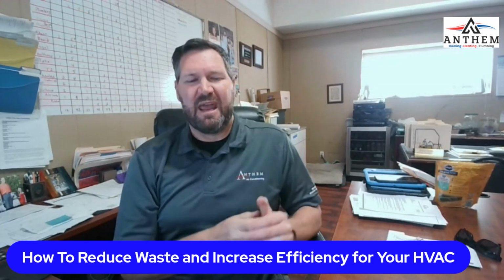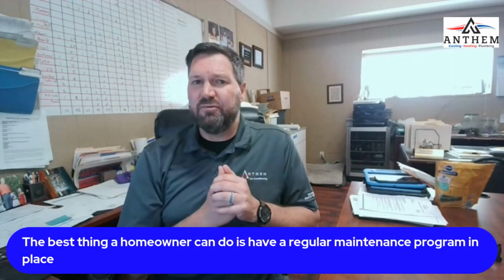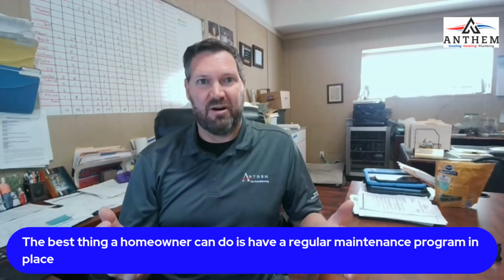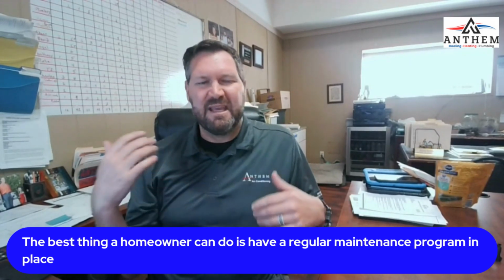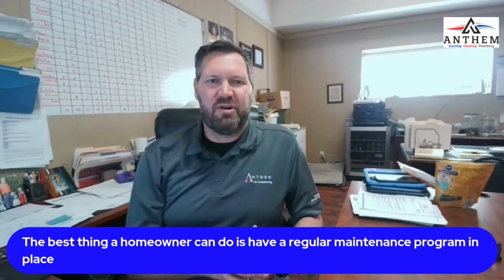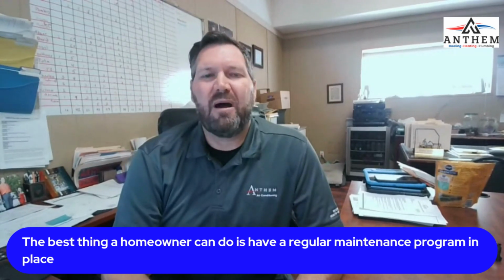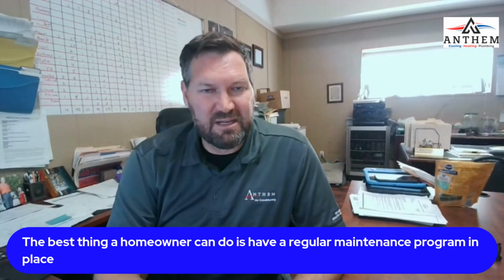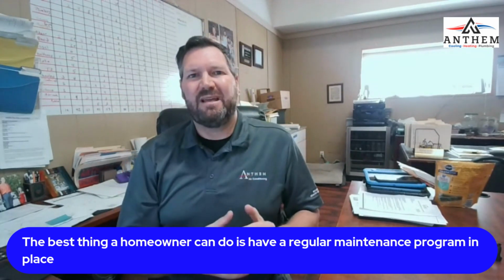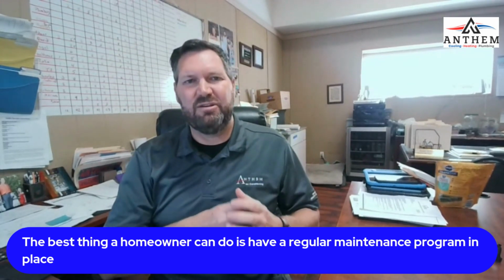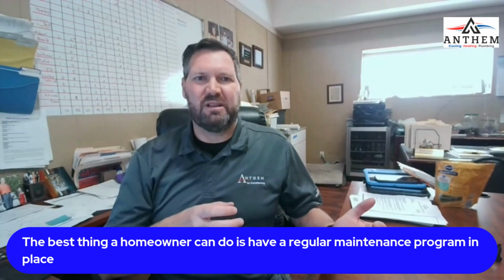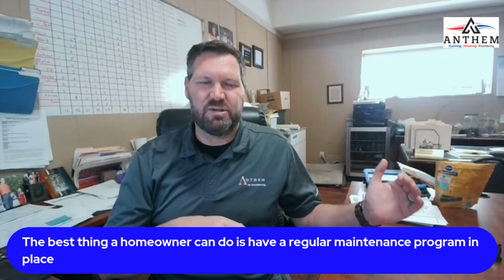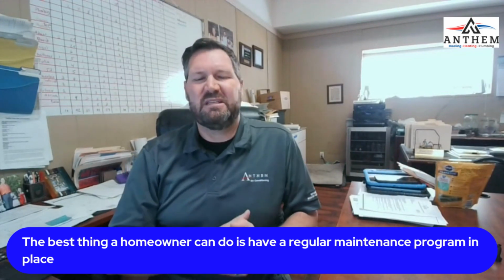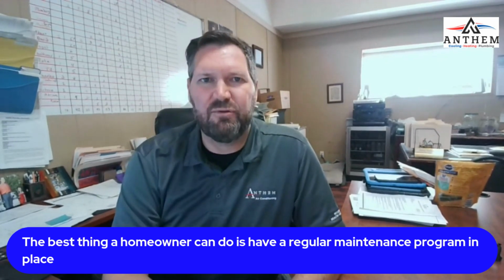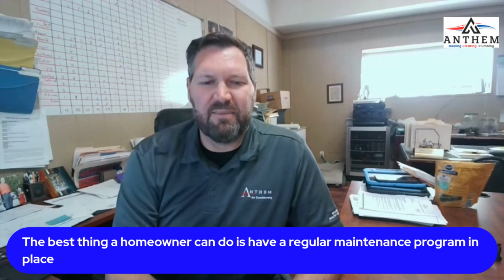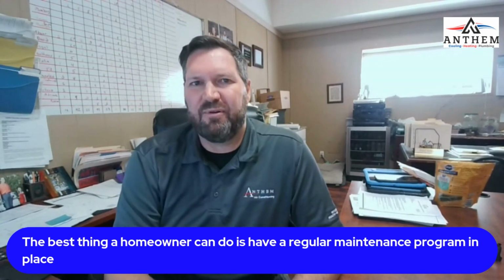Also, clean motors and fans inside your air conditioner systems. It's going to reduce amp draws on those motors, which is energy draws on those motors. When you have dirt on your fans, it creates a drag. Same thing with your motors, that causes them to work harder. Proper refrigerant levels in your air conditioner system are needed to make sure that you are maximizing the amount of cooling capacity in your system. When you don't have the proper refrigerant levels, whether it's charged too much, meaning too much refrigerant in the line, or too little, then your system basically cannot cool at the efficiency level it needs to, if at all. So you could end up with problems when your refrigerant levels are not properly set.